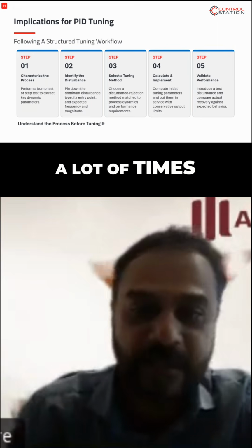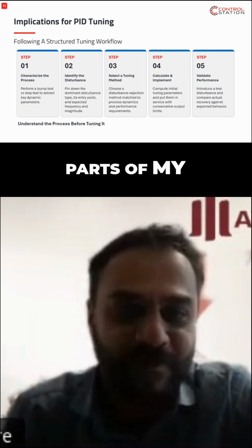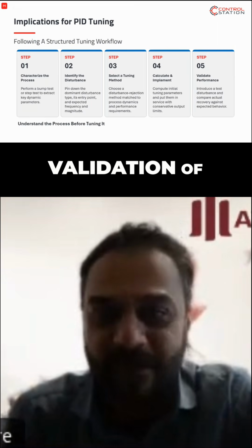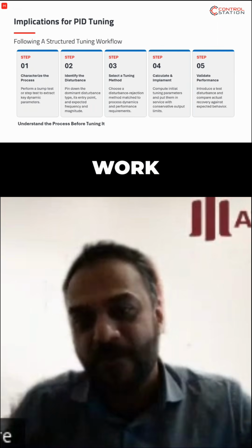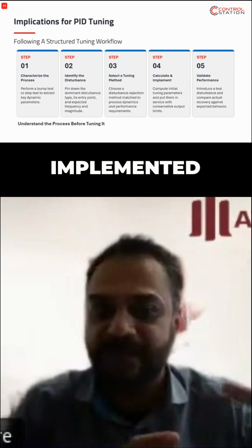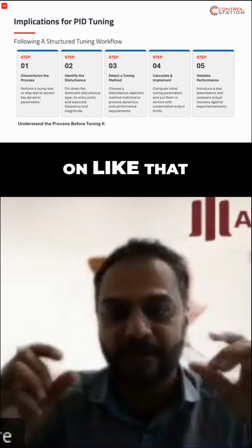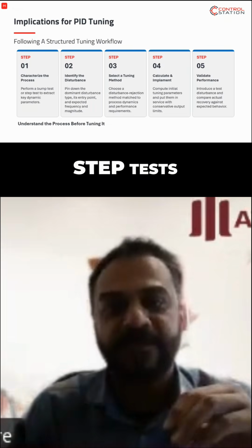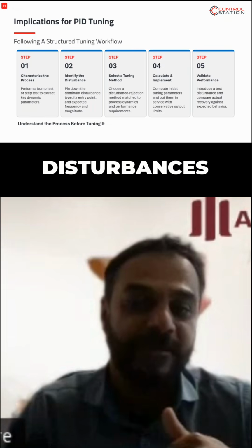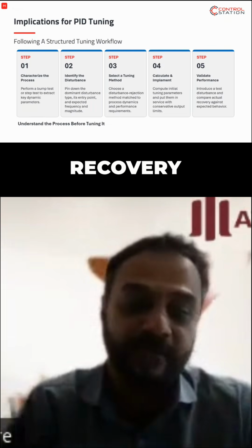And a lot of times, one of the satisfying parts of my on-site commissionings is the validation of performance. Once you've done your work, you followed your process, you implemented these tunings, and you're working on the last 10%, do step tests, look into the test disturbances, and then compare the recovery against expected behavior.